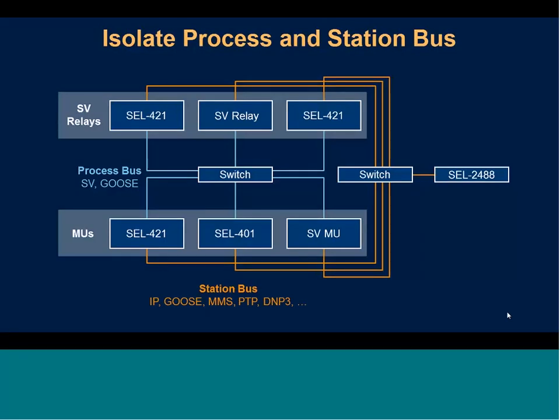This is all of our protection data, and so we use two different protocols to transmit it. The sampled values protocol in 9-2 transmits our analog signals, so our CT and PT signals, and then GOOSE is used to transmit digital or discrete data.